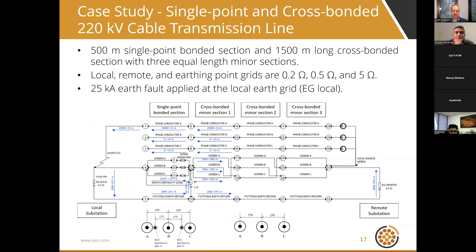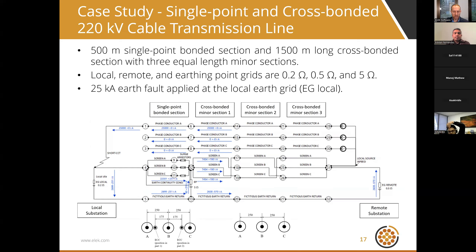Case Study 2 involves a complex 220 kV cable transmission system. On the left-hand side is a single-point bonded cable system with an ECC conductor connected between nodes four and twelve. On the right-hand side is a cross-bonded system, which is also transposed — the screens are transposed to cancel the induced currents. The earth fault current distribution has been analyzed for this scenario, which is more complex due to all the mutual coupling and return paths involved.